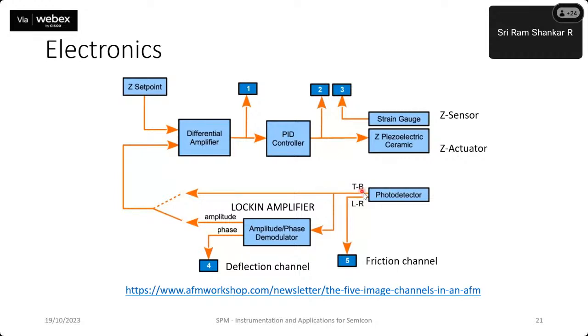We have the photodetector from which we generate two signals: top minus bottom, and left minus right. The left minus right gives you the friction channel imaging, in case you are maintaining continuous contact with the sample. The top minus bottom is now a sine wave, which we feed to a lock-in amplifier, a demodulator, to measure the amplitude and phase. We use the amplitude to regulate the overall tip-sample interaction, while the phase we use to look at the material contrast.